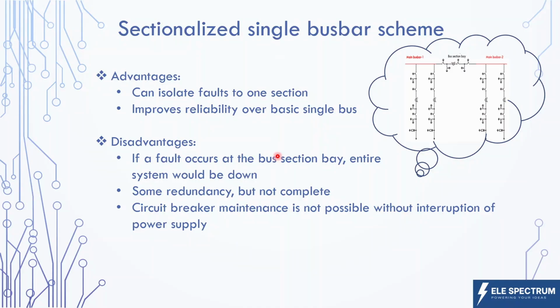In terms of disadvantages, it is more or less similar. If a section has any kind of fault, then that complete section will go out of operation. And similarly with the circuit breaker, if we want to maintain one circuit breaker or if there is a fault in one circuit breaker, that complete feeder will be out of operation. So this is also a kind of bus bar scheme which is majorly used for distribution substations. Now let's move on to our next bus bar scheme.